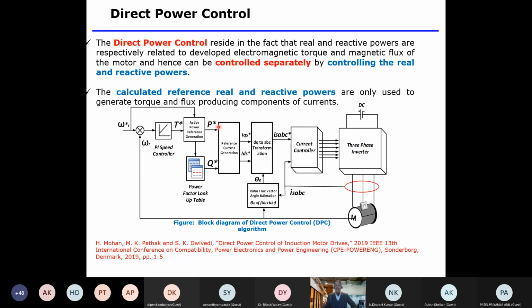From the torque controller output and the actual speed, we calculate the real power reference, and from this and the required power factor, we calculate the reference reactive power.